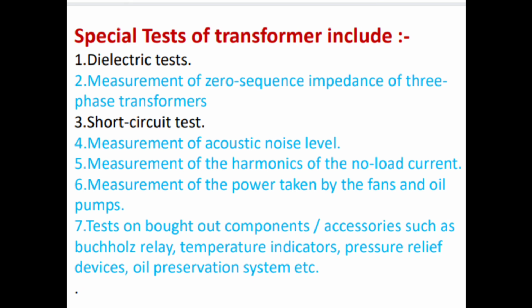So the dielectric test is under the special test. Second is measurement of zero sequence impedance of three-phase transformers. Third is short circuit test. Fourth is measurement of acoustic noise level. Fifth is measurement of the harmonics of the no load current. Sixth is measurement of power taken by the fans and oil pumps. Seventh is test on component accessories such as Buchholz relay, temperature indicator, pressure relief device, oil preservation system, etc. Special test is carried out only for a specified purpose, and in this the dielectric test is included.